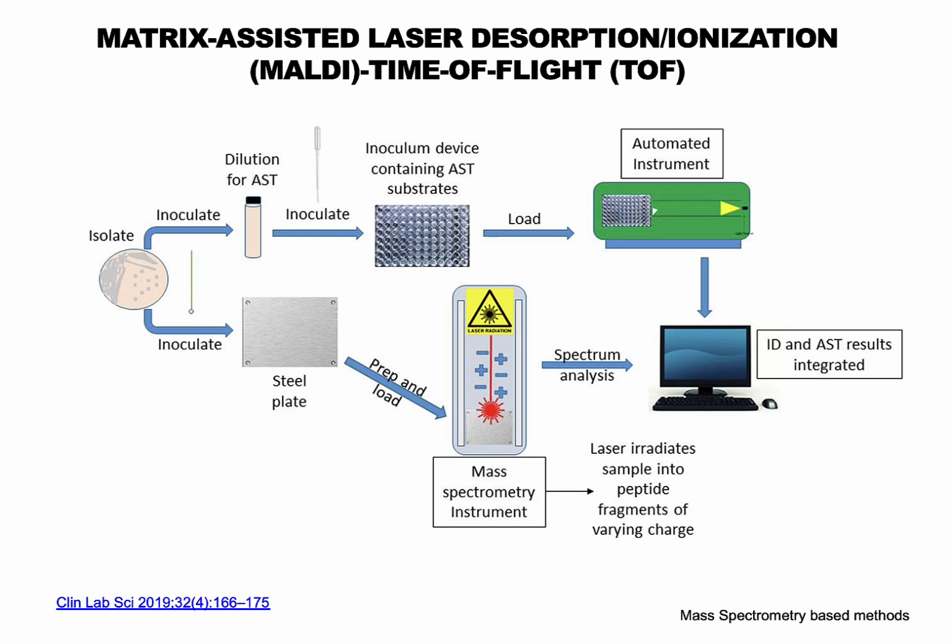The sample and reagent mixture is exposed to a high-intensity pulsed ultraviolet laser, which causes the ejection of gaseous ions produced from the microorganism's various chemical components. These gaseous ions are collected and accelerated through the mass spectrometer, with their velocity determined by their mass-to-charge ratio, resulting in different arrival times at the detector.